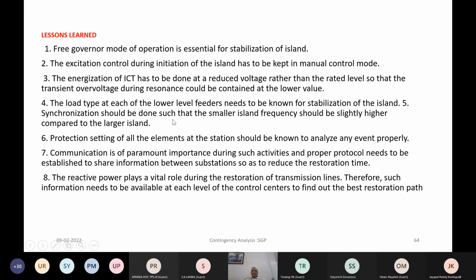Synchronization should be done such that the smaller island frequency should be slightly higher compared to the larger island frequency. This is very important. The larger island will stabilize the incoming frequency from the small island. So the small island, which is driven by a black start unit, should have a slightly higher frequency when you are closing the breaker, so that the power flow can be accordingly.